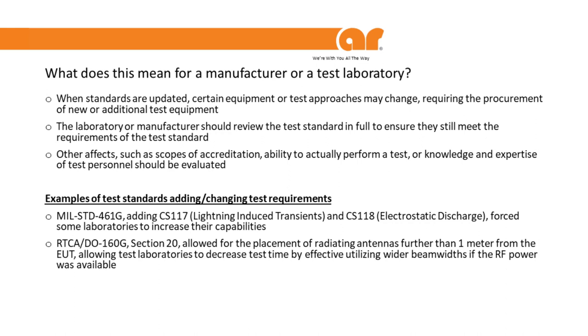When a test standard gets updated, what does that mean for you as a manufacturer or test laboratory? Certain equipment or test approaches may change, requiring the purchase of new equipment. For example, if you were a MIL-Standard 461 test house and they include lightning and electrostatic discharge, and you don't have any of that equipment, you'll have to go get it — and it can be a major investment. If you were already testing DO-160 and other things, you may already have it, but you need to ensure your equipment meets the requirements of the new standard.